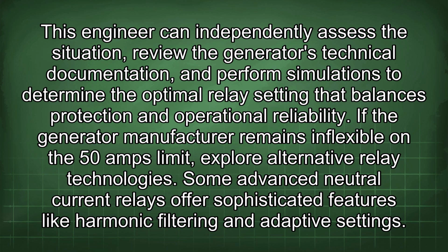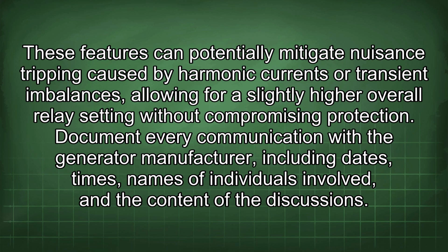If the generator manufacturer remains inflexible on the 50 amps limit, explore alternative relay technologies. Some advanced neutral current relays offer sophisticated features like harmonic filtering and adaptive settings. These features can potentially mitigate nuisance tripping caused by harmonic currents or transient imbalances, allowing for a slightly higher overall relay setting without compromising protection.